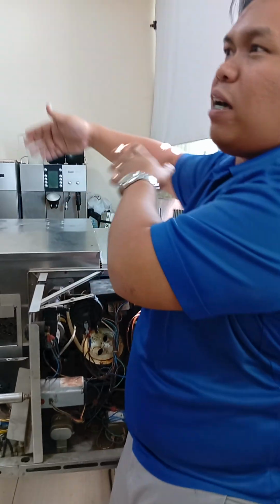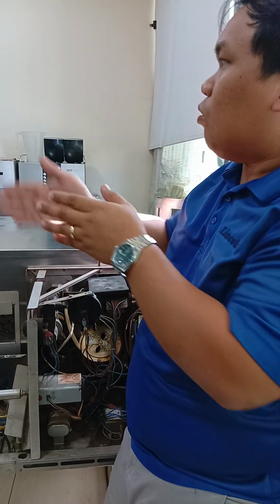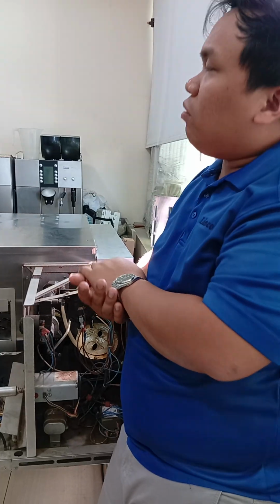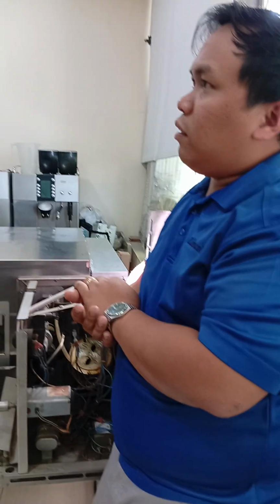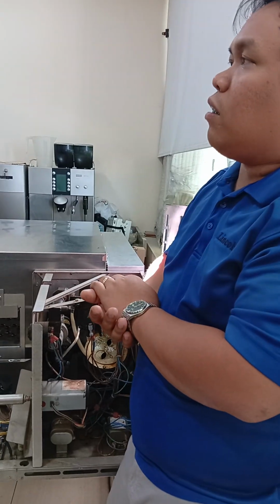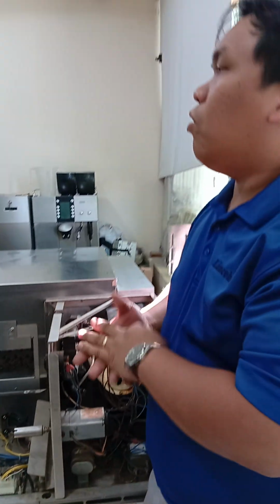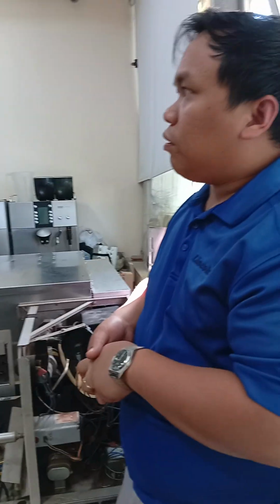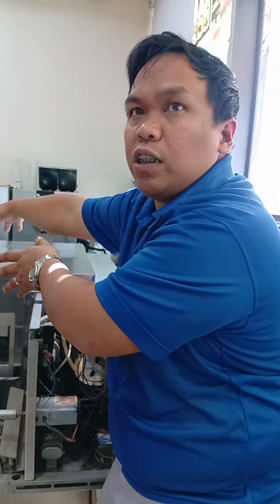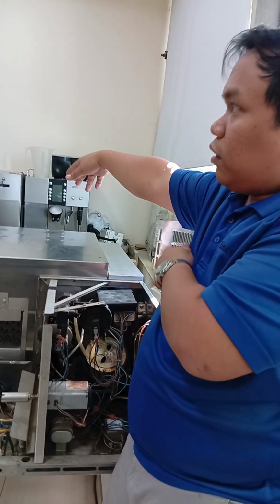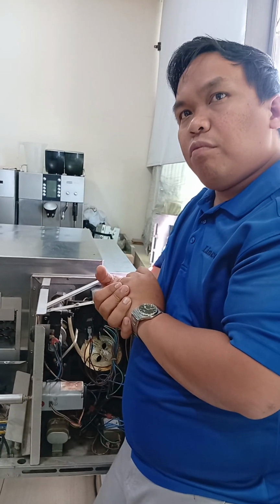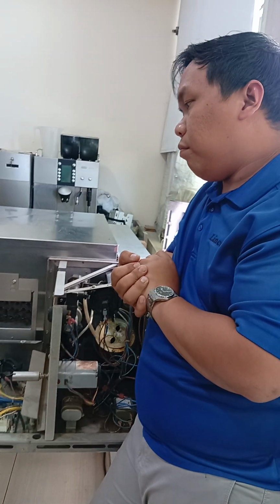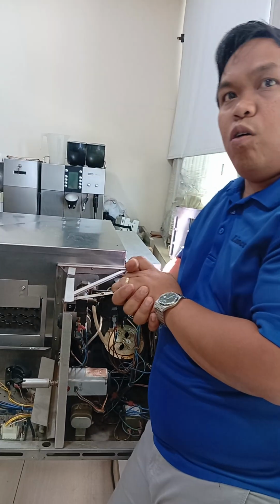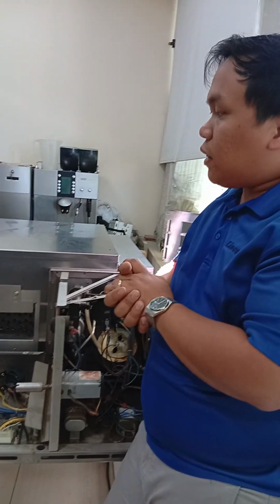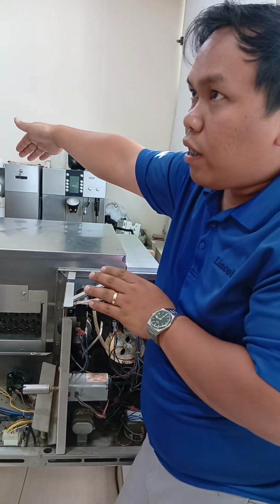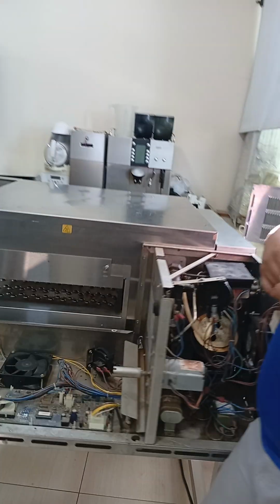Okay? They might forget. For example, you did the installation, you did the training, and then you see there's a lot of grease or something, meaning they are not following the standard daily, weekly, and quarterly inspection. Okay, this is part of the operation side. So if we talk about the operation side, let's take it daily, weekly, and monthly. Yes.